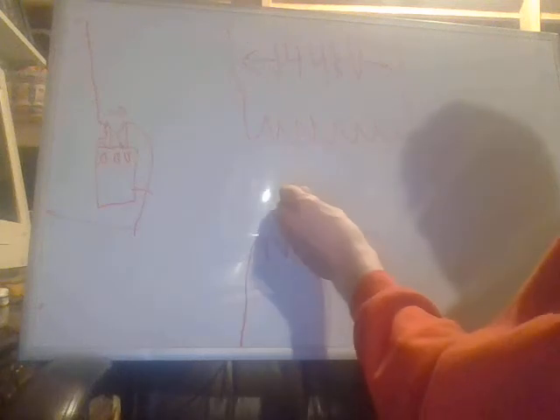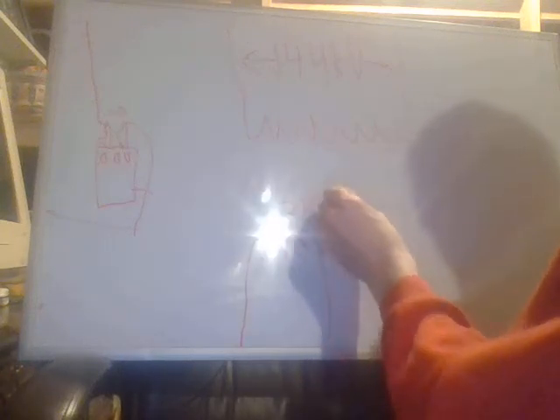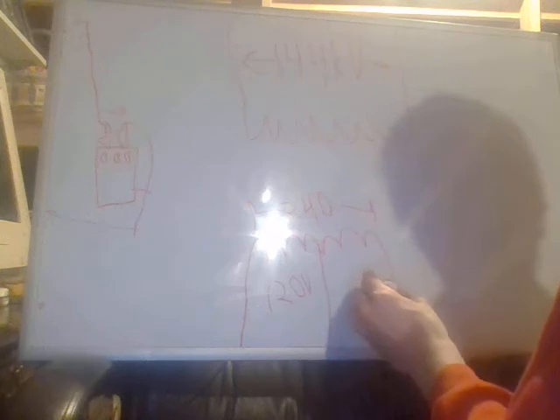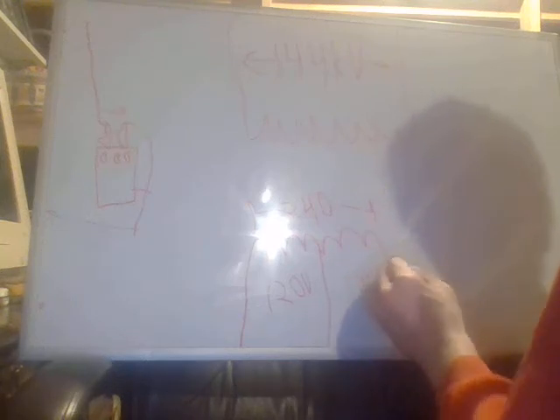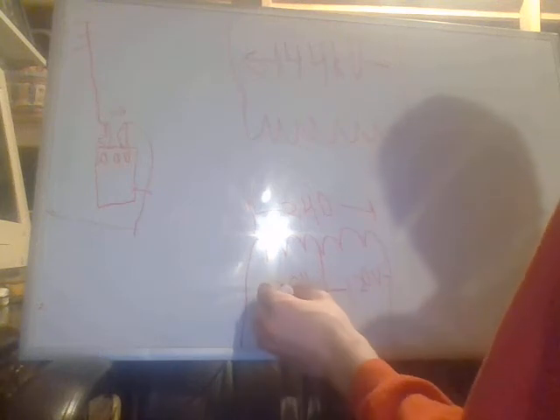But also in the middle, a neutral wire. Since the phase shift from this half to this half is 180 degrees, we're basically just splitting it in half. We can do something where we can just double the voltage. So this is a 240 volt transformer across the entire winding. But also, since it's split in half, 240 divided by 2 is 120. So 120 volts and 120 volts.